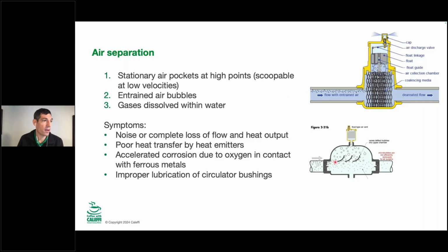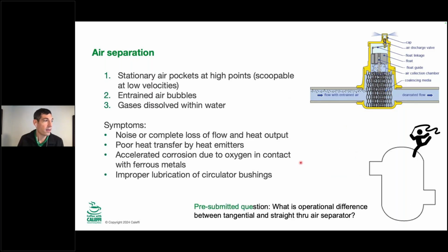One of the things we had is another pre-submitted question here, and this is an analogy that you probably did not see coming today: a tangential separator. Let me switch over to a different pointer here. I'm going to use a pen. A tangential separator is used mostly in commercial. I don't know that I've ever seen a residential one. It's going to have offset inlet and outlet of the air separator, and the idea is that it's going to create kind of a vortex in here and spin around, so the air is able to come out to a vent in the top here. Like ribbon dancing in the Olympics, it's only really worthwhile if it's spinning around a lot. So if you have a really low flow rate here, all those air bubbles are just going to go straight across.